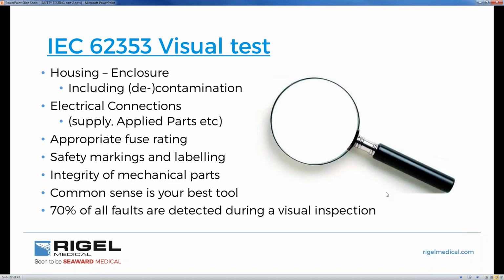The visual check. What do you look at for a visual check? You want to make sure that the enclosure, including contamination or decontamination of the medical device, is good. We want to make sure that any electrical connections, power supply, applied parts all look good. Does it have the appropriate fuse rating? Very important. If you have a medical device that should have a 3 amp fuse, and the fuse that is in the device is actually much higher, 10 amp, 13 amp, then it's an inappropriate fuse. Very important in electrical safety.